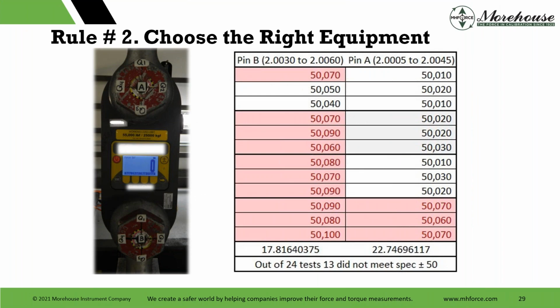Choosing the right calibration equipment. Here's one. Manufacturer specification is 0.1% of full scale. It's plus or minus 50 pounds. All we are showing in this example is this pin, the shackle, this cast pin at the top, bottom. It's marked in different quadrants. And all we are doing is turning that pin. We're not taking it out, we're just turning it.